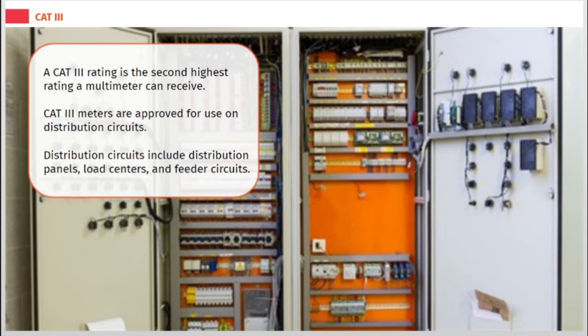A CAT 3 rating is the second highest rating a multimeter can receive. CAT 3 meters are approved for use on distribution circuits. Distribution circuits include distribution panels, load centers, and feeder circuits.